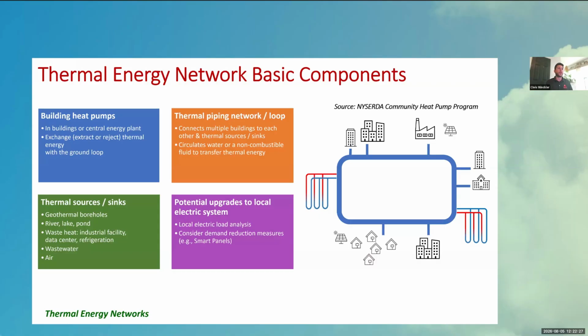So a clay horizontal system will perform equally and sometimes better than a vertical system, depending on what that vertical system is installed into. But as we start doing larger systems, you just don't have enough space to do a horizontal. To put it in perspective, if you have an average, say, 2,000, 2,500-ish square foot house, the average pit that you would need to dig to heat that house ends up being somewhere between 40 and 50 feet wide by 100 feet long by 6 to 8 feet deep. So it tends to be 3-4 times as big as what you would even need for a septic system if there wasn't city sewer available. So it's really just a lot of space required for a horizontal.